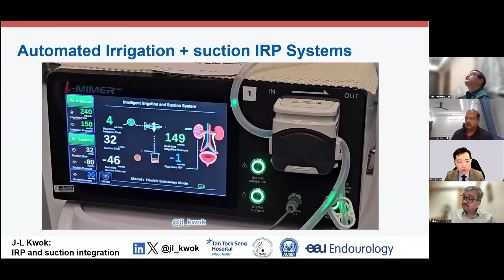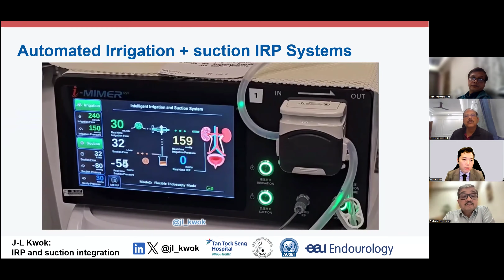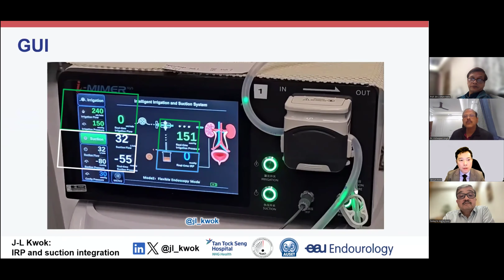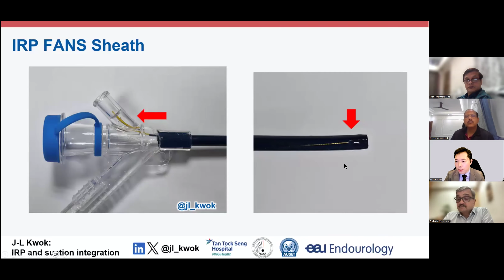So this is how it looks in real life. You may look at a lot of numbers, but the color coding is quite important. The green is the irrigation flow in, the real-time pressure. The white shows the out, which is the suction flow, the real-time suction pressure, and blue is the real-time IRP. So this is a FANS sheath, and if you look at the third port, which is an IRP monitoring port, that is a pressure wire that goes all the way to the tip, and you see the apertures at the tip, which is where the pressure is sensed.